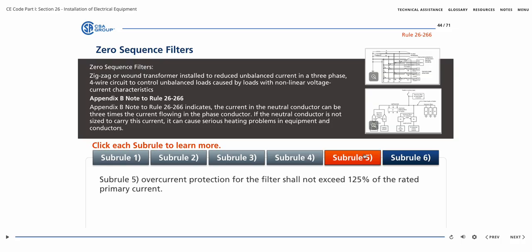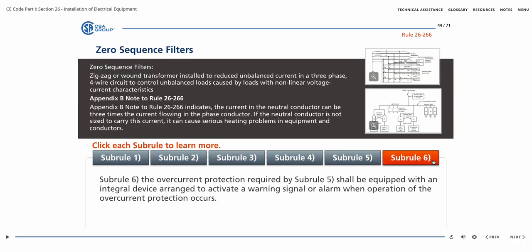Sub-Rule 5. Overcurrent protection for the filter shall not exceed 125% of the rated primary current. Sub-Rule 6. The overcurrent protection required by Sub-Rule 5 shall be equipped with an integral device arranged to activate a warning signal or alarm when operation of the overcurrent protection occurs.